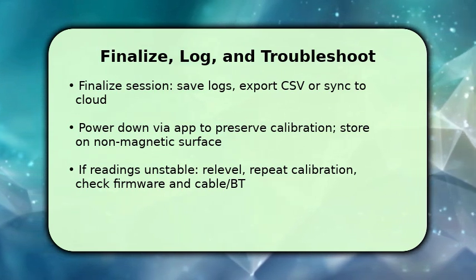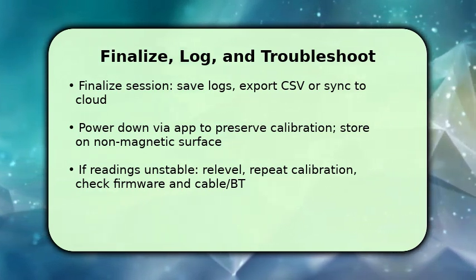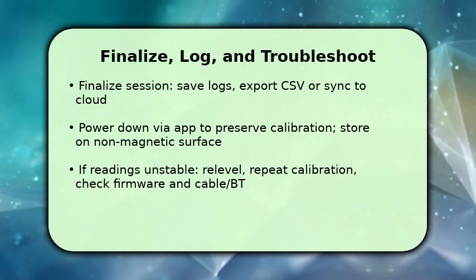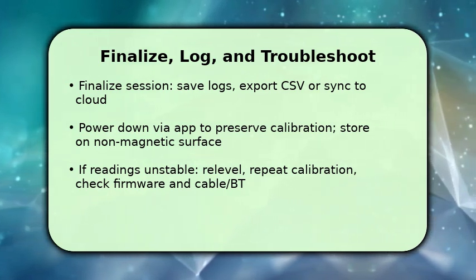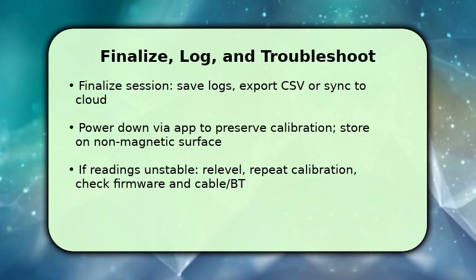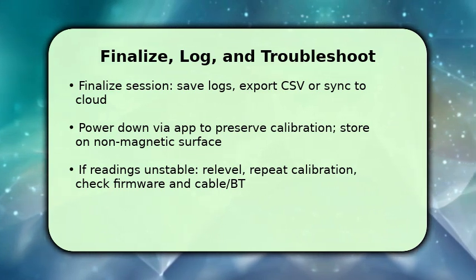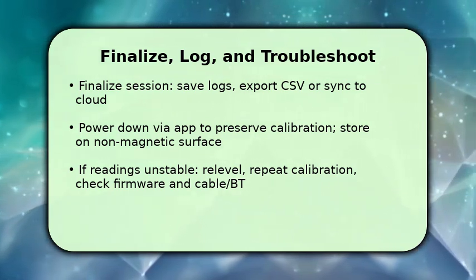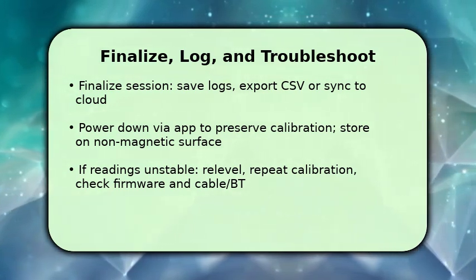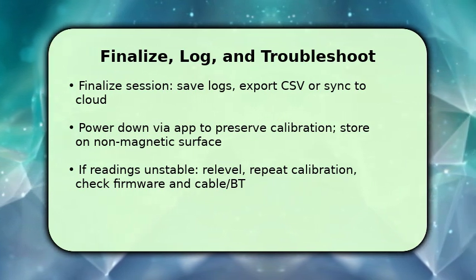If readings become unstable, relevel the unit and repeat the calibration. These 2 steps resolve most issues. If problems persist, update firmware and inspect the cable or Bluetooth link. Faulty connectivity or outdated firmware often causes persistent drift or missed samples.